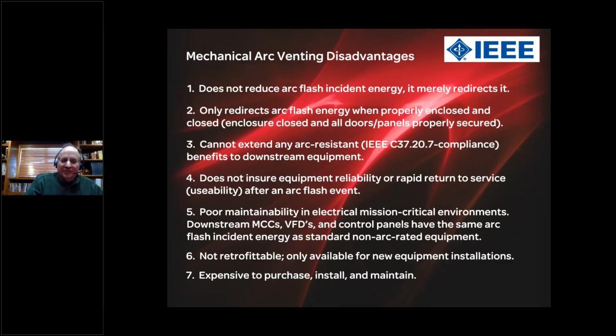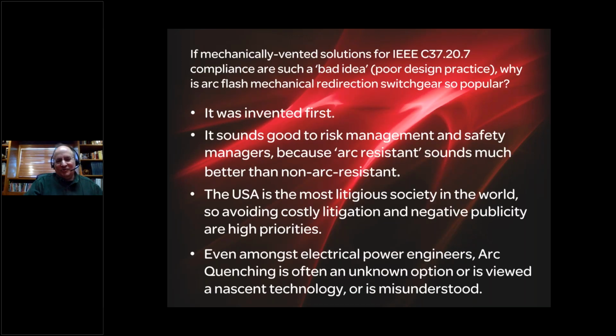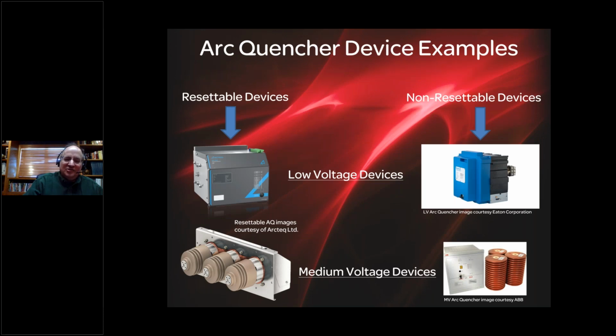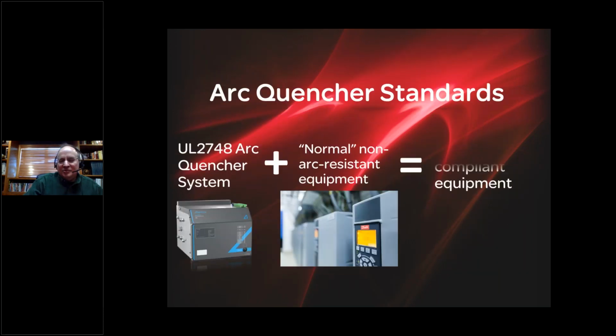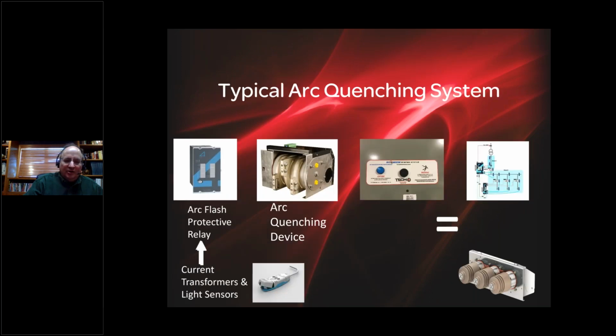If there is a fault event in the downstream device, it's what I like about electricity. It travels just shy of the speed of light. So the CTs, I want to be clear here. When I showed current transformers and light sensors, I do not need to add another set of CTs in the drives or the MCCs. I only need CTs up by the quencher, in whatever equipment is feeding that gear. So the only thing I'm extending downstream to the MCCs and the drive cabinets are my light sensors. That's all. I only need one set of CTs for the entire system. Good question. Thank you.